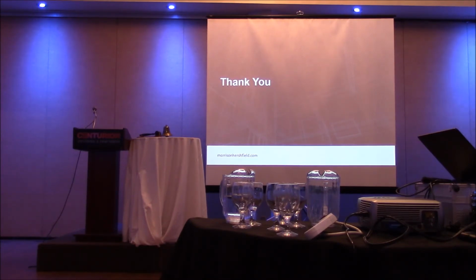We also use it when we're doing motor protection, because the motor manufacturer builds the motor to withstand locked rotor amps, the starting current that goes through, because it's a lot more current. So it generates a lot of heat as it goes through the conductor. They use that value to create a protection curve for the motor. So very large motors have a certain number of starts they can do in a period of time because they have to cool down between each start. So it could be measured in hours, it could be measured in days.